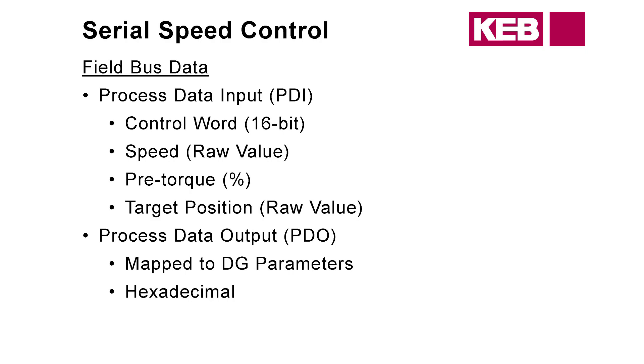Not only are we looking for values coming from the controller, we're also sending values back out to the controller, because the controller is expecting certain outputs from our drive. Those are referred to as PDOs — process data outputs. They are mapped to DG parameters in the drive. The DG parameter list contains parameters used for diagnostics; they are read-only. If you're using COMBIVIS, these are the parameters you would scope, and they are in hexadecimal format. So anytime we're dealing with serial, we're likely entering a hex number.